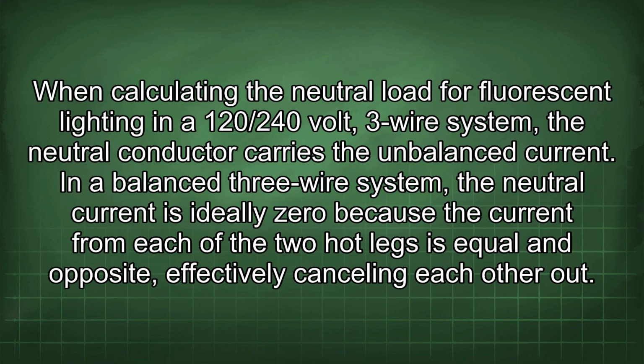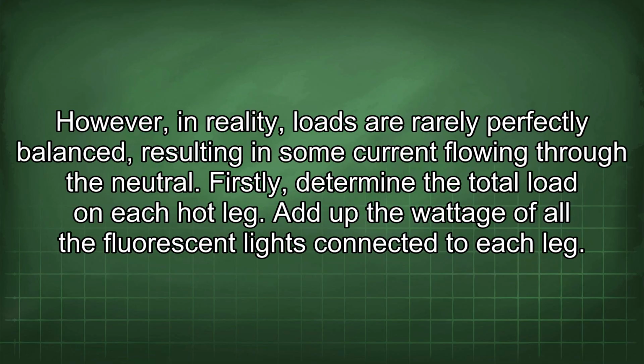When calculating the neutral load for fluorescent lighting in a 120/240 volt, 3-wire system, the neutral conductor carries the unbalanced current. In a balanced 3-wire system, the neutral current is ideally zero because the current from each of the two hot legs is equal and opposite, effectively cancelling each other out. However, in reality, loads are rarely perfectly balanced, resulting in some current flowing through the neutral.